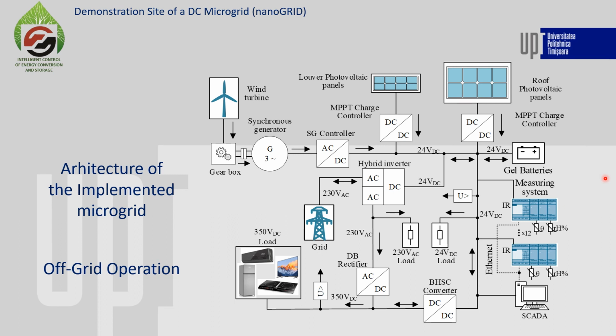The connection to the AC grid, as you can see, is done through this hybrid inverter, which has the DC output connected to the low voltage DC bus system. Also, the AC loads are supplied by the hybrid inverter, and from this AC bus, the high voltage DC bus can be supplied using this diode bridge rectifier. This diode bridge rectifier was implemented as a backup solution for an eventual failure of the bidirectional hybrid switch capacitor converter. That's because this converter was developed and built by us, and of course we are expecting to have some eventual issues with it.